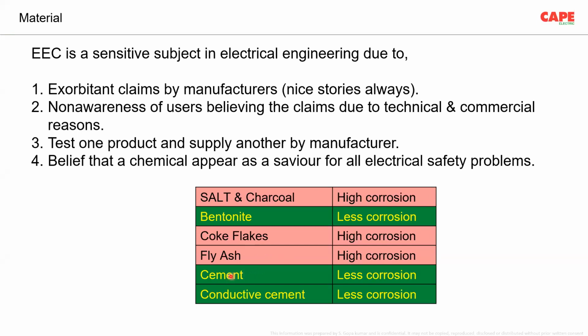You can also use cement. Cement in the sense you use normal cement. This also sometimes works very well. And you can also have the fourth material, conductive cement, less corrosive. Basically, these 5 are the materials which are used, out of which these 2, coke flakes and fly ash, are the commonly used materials with a lot of stories, and the resistivities are quite less. But the problem with these 2 materials is they corrode your electrode quite fast.